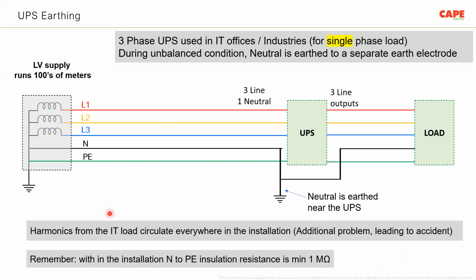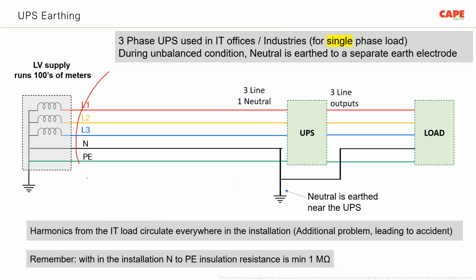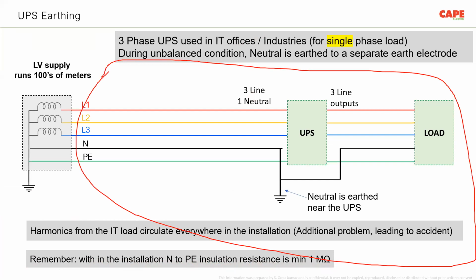Now, the last one. Remember, within the installation, neutral to PE insulation resistance is minimum 1 megohm. What I mean is, from this place where I am making this red round, this is your installation. Before that, you have the transformer. After that, you have the installation. Within this installation, you have 4 current carrying conductors, 3-phase and neutral. Then you have a PE conductor. So here you have 3 + 1 current carrying conductors and a PE conductor.